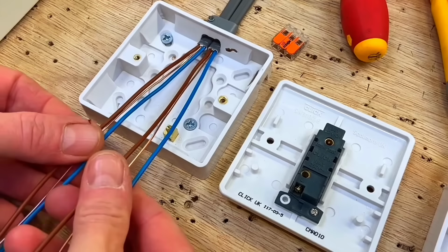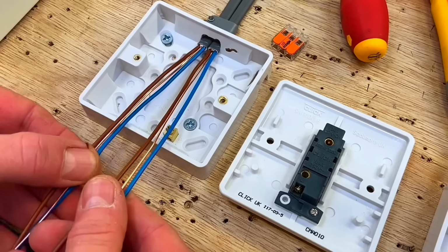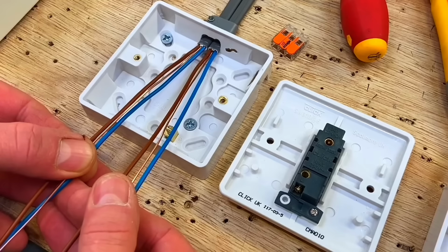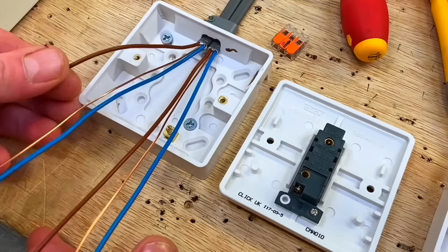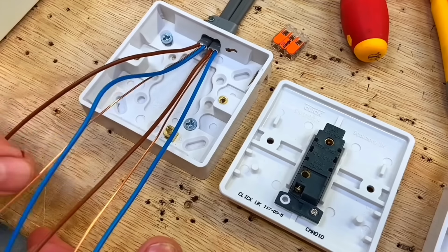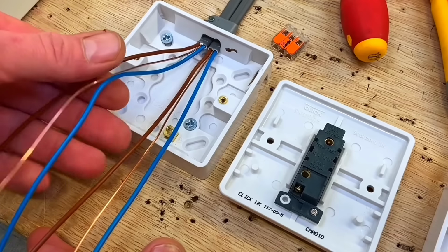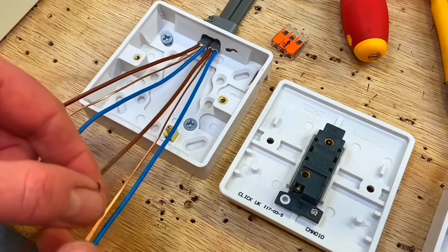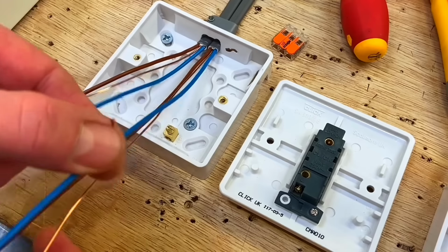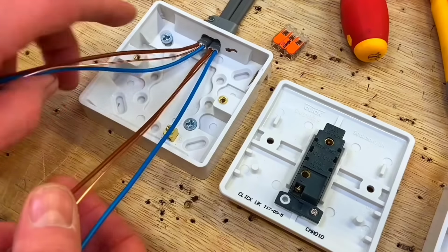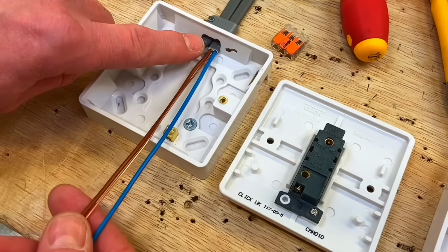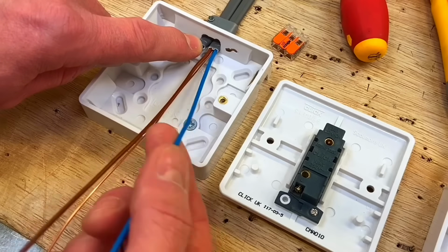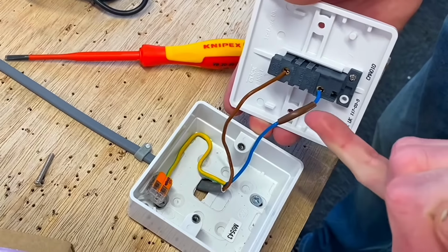Subtle difference to all the other lighting circuits that we've wired at college is that we've now got 2 cables. We've got 2 twin and CPCs here. We've got the feed coming in, so we've got a line, a neutral and a circuit protective conductor coming in, in this case from the consumer unit. And going out, we have a switching line, a CPC and another neutral. I know at some colleges where there is, say, one cable coming down to a switch of twin and CPC, often the blue is a switching line conductor and is identified with brown sleeving.